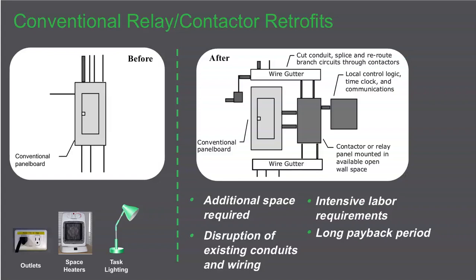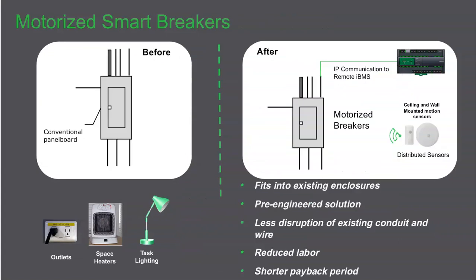Before, you had to power some type of circuit breaker and add a relay panel with multiple devices, spending extra labor. Nowadays they have motorized breakers, so before and after almost look the same. You can pick and choose which breakers are motorized in the panel, so you can do some lighting control too. Some panels now come with CTs already built into every circuit, so you can get into plug load analysis, not just control but monitoring KW and KWH. You can also tie in wireless sensors, getting more intelligent than before, with some cost savings.